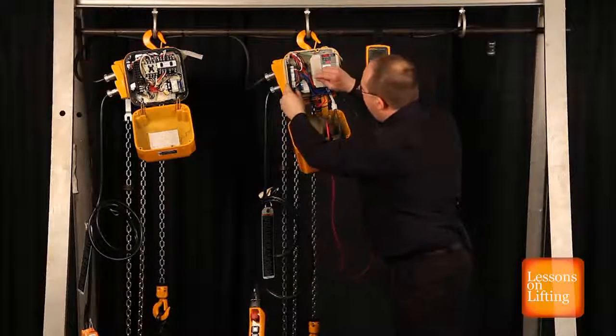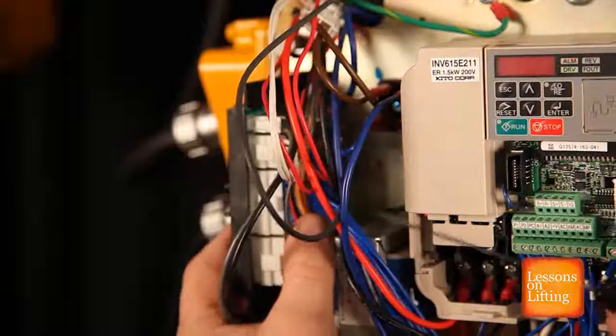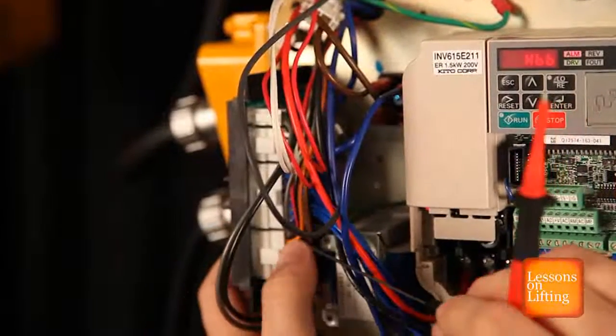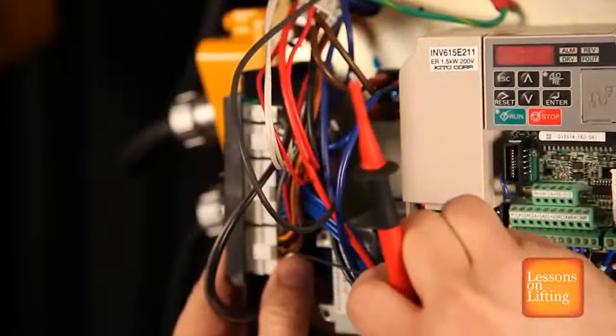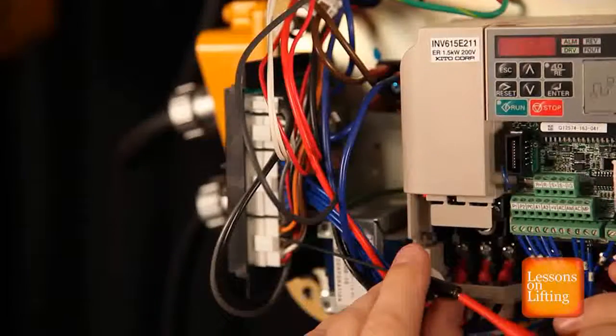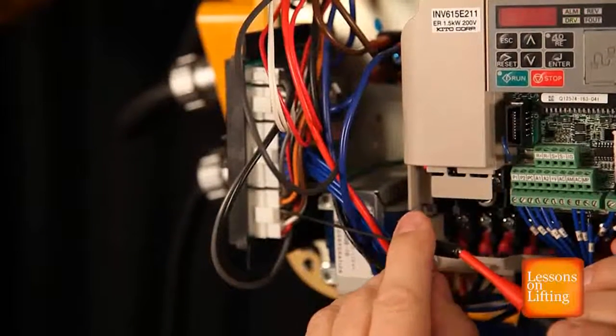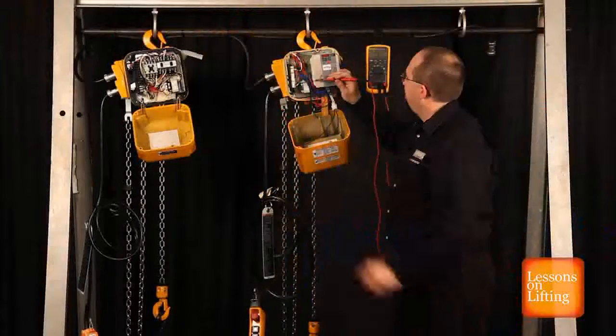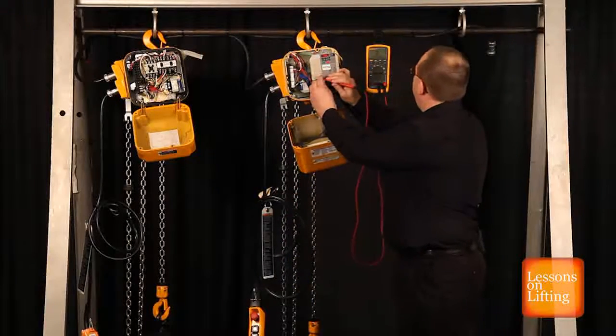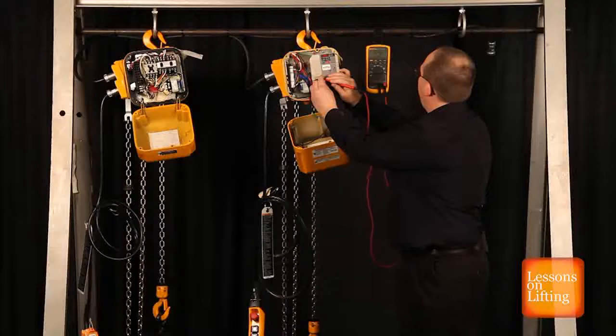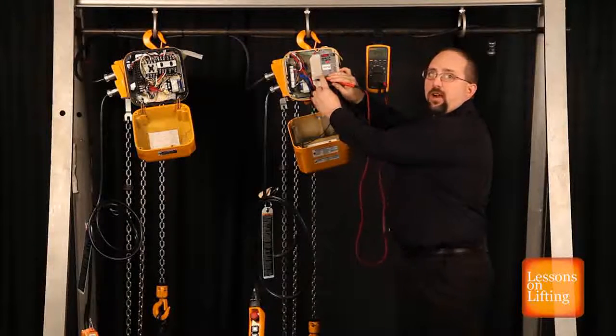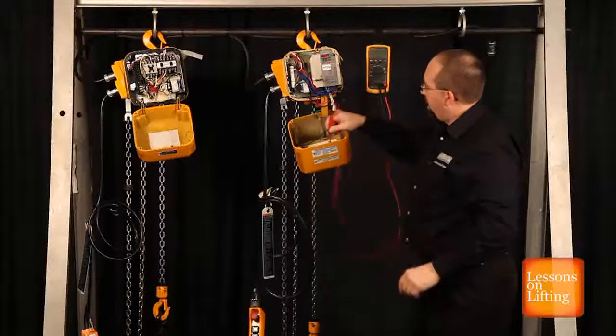So at CN11, we'll stick our probe down in there. Be very careful when you're back probing these things that you don't back probe the wrong wire. Make sure that your jumper pin or your back probe is not shorted against anything else. So we back probe that pin and we see 125 volts. All right, we know the fuse is good.